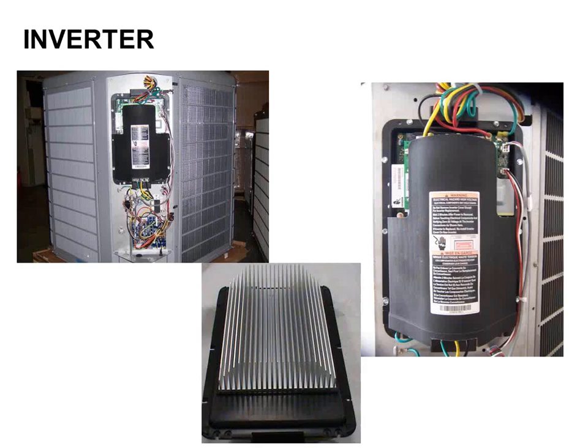Here's what an inverter typically looks like. This is just one style. There's numerous different types. But this black box, if you will, is the inverter hanging off the side of this condensing unit. And obviously there'd be a weather enclosure cover on the front of it. I took it off for the purposes of pictures here. On the back side of the inverter, you'll see in the bottom picture there's a heat sink. That guy's in the inside of the unit, and air is blowing across him. Inverters do have a lot of waste heat.